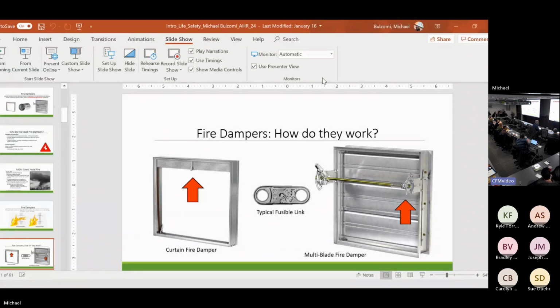When I have a really big opening in a mechanical room or a shaft wall or something, and I've got a 200 by 200 damper, I can't put like 20 of these panels in a row and just make them like 6 sections long, 4 sections high. That damper will fall to pieces. There's going to be a lot of blades and frames in the airstream, and it's going to be really difficult to pass the test. So as a function of passing the test, we switched to this multi-blade fire damper.